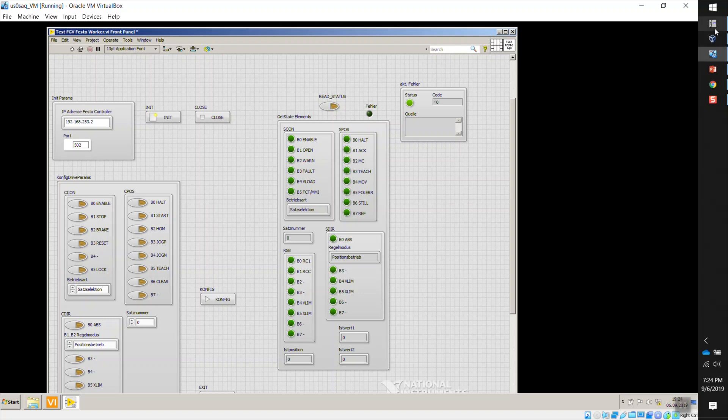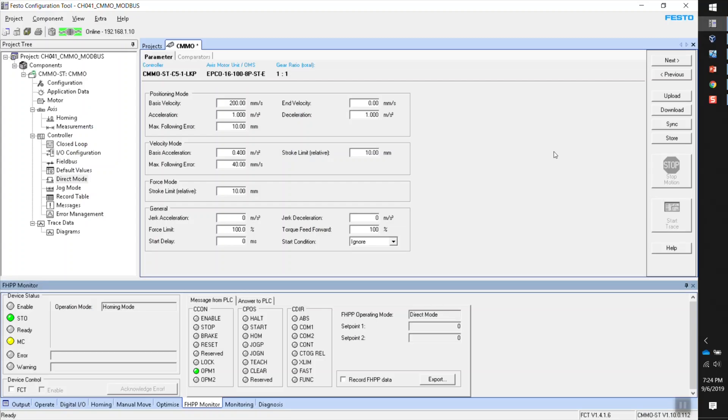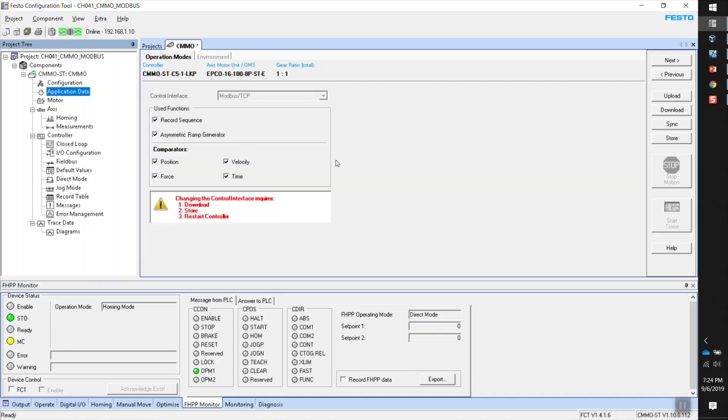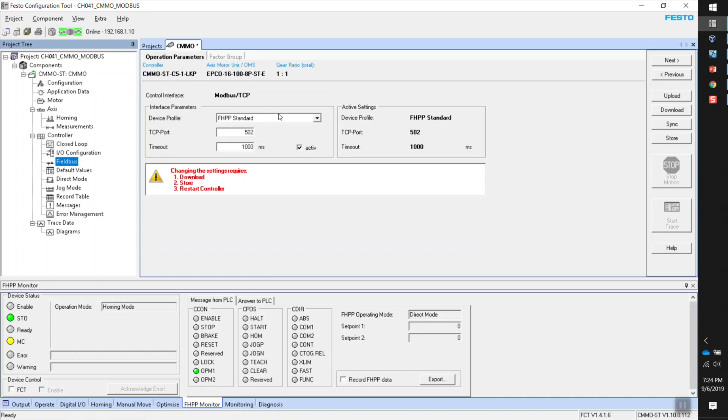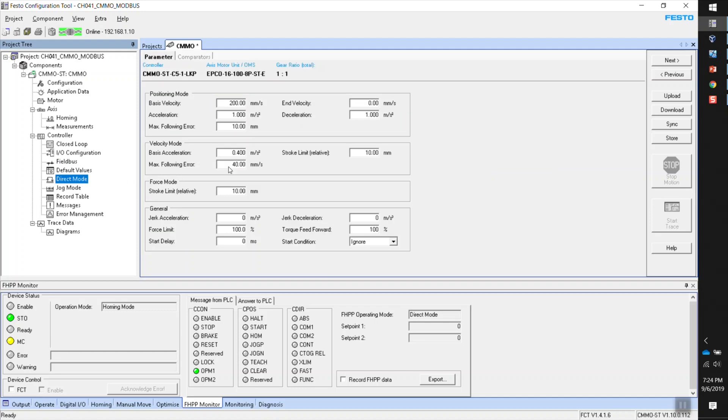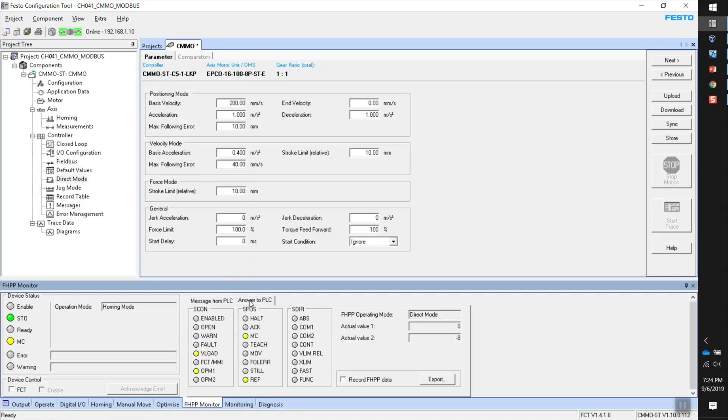So before I keep going here with the National Instruments environment or the LabVIEW environment, let me go one step back. In terms of the configuration in the Festo Configuration Tool, I really don't have anything special here. The only thing that I have here, it's Modbus control interface, Modbus TCP. For this example, I'm using a CMMO-ST LKP. This is the one that supports Modbus communication. What else did I change here? I don't have anything special here under field bus. I just have FHPP standard, port 502, and then a timeout of 1000. I didn't change anything there. I'm just going to leave FCT open here so I can monitor. I can use this FHPP monitor to see what's coming from the PLC or from LabVIEW in this case and what I'm sending to LabVIEW.